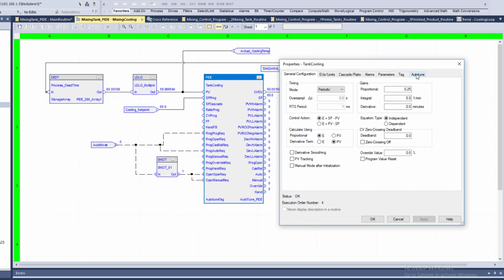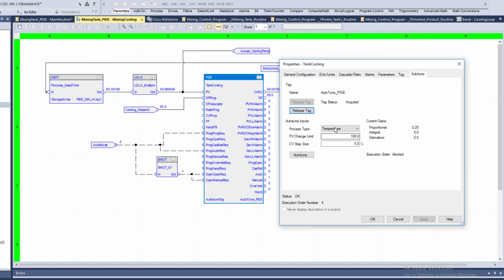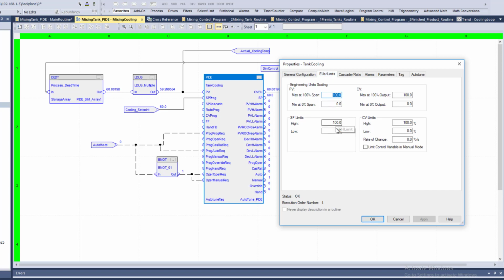Okay, so what we're going to do is go to auto tune and our step change is actually added, right? So our change rate, we do not want to change over 100. We're actually controlling it from, I believe, the set points inside of here are from 100 to 0. We can change that to whatever we want to. But again, when it comes down to it, that's limiting the factors, right? So it depends on what your low cooling point is.